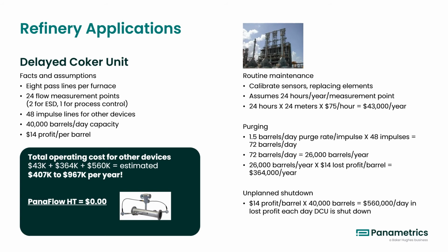Last is the unplanned shutdown due to flow measurements not agreeing with each other, or loss of measurement due to a clogged impulse line or membrane. With $14 profit per barrel and 40,000 barrels per day capacity, it leads to $560,000 in lost profit each day a delayed coker unit is shut down. Therefore, a reliable ultrasonic flow meter just makes sense in the long-term operation of a delayed coker unit.